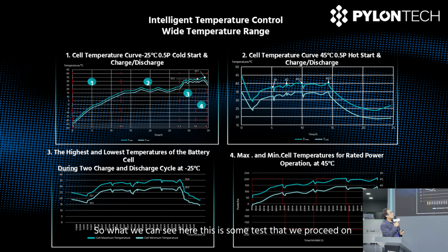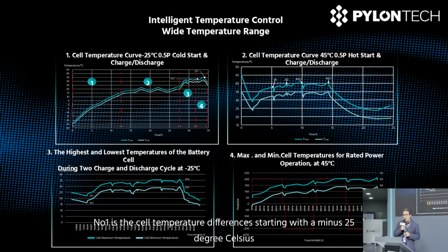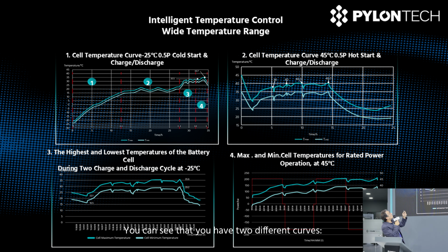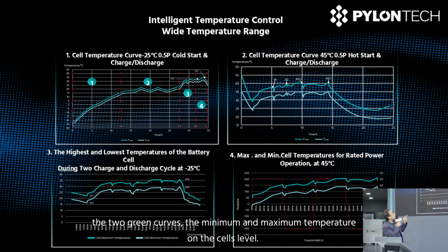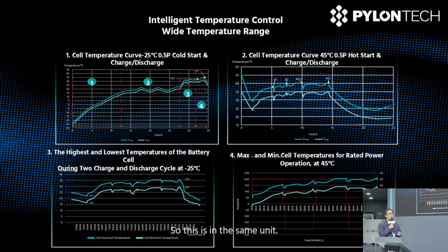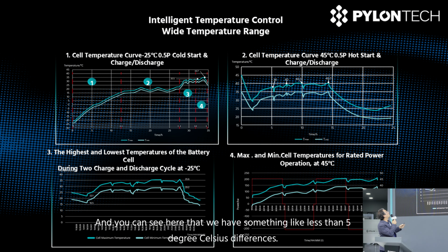So what we can see here is some tests that we proceeded. It was on the container solution, I think so. So what we can see on the above left side, the figure number 1, is the cell temperature differences, starting with minus 25 degrees Celsius. You can see that you have two different curves, the two green curves, the minimum and maximum temperature on the cell level. So this is in the same unit. And then we started at minus 25 degrees. And you can see here that we have something like less than 5 degrees Celsius differences.